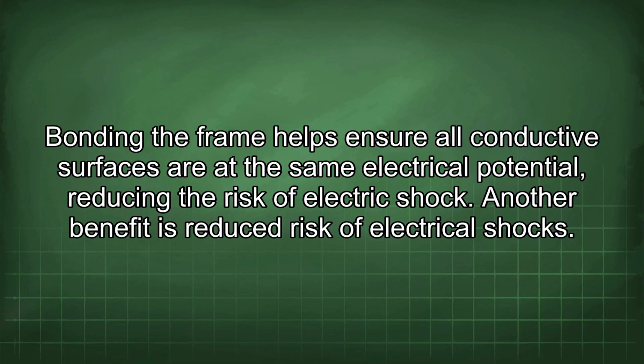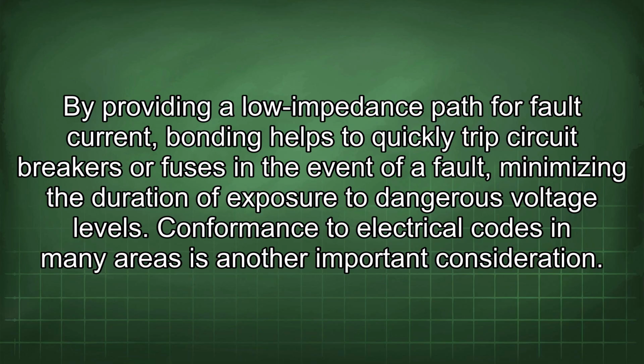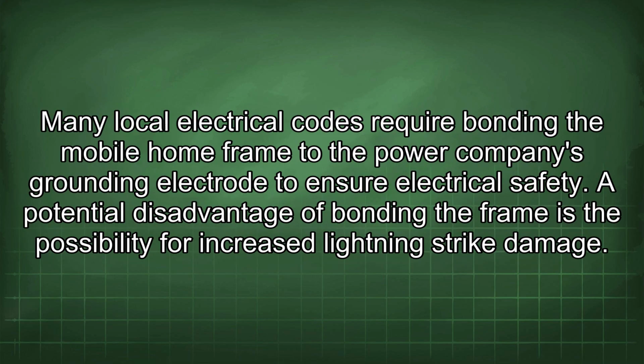Another benefit is reduced risk of electrical shocks. By providing a lower impedance path for fault current, bonding helps to quickly trip circuit breakers or fuses in the event of a fault, minimizing the duration of exposure to dangerous voltage levels. Conformance to electrical codes in many areas is another important consideration. Many local electrical codes require bonding the mobile home frame to the power company's grounding electrode to ensure electrical safety.